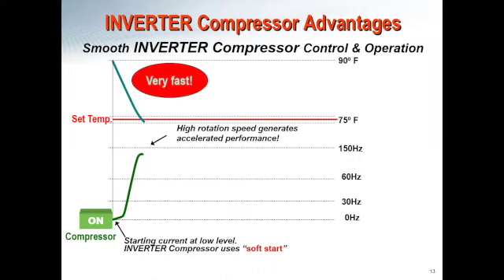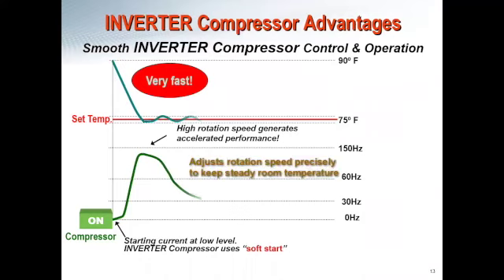We go all the way up to about 130 hertz, which is allowing VRF technologies to drop the temperature from whatever it may be, in this instance 90 degrees Fahrenheit, all the way down to that 75 degree temperature very quickly. This is really just due to the extremely high rotational speeds on inverter compressors as opposed to more traditional compressors. And then once we hit that set point, we don't turn our compressor off almost ever.